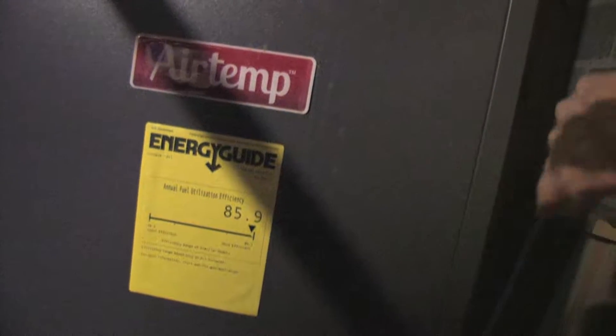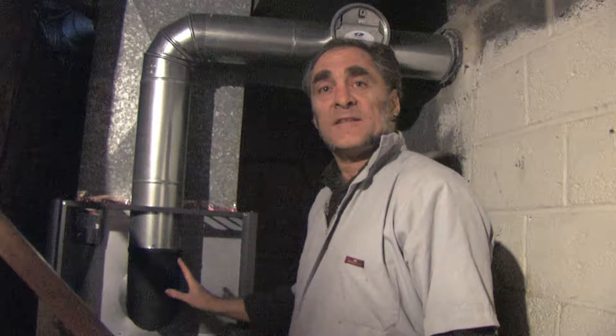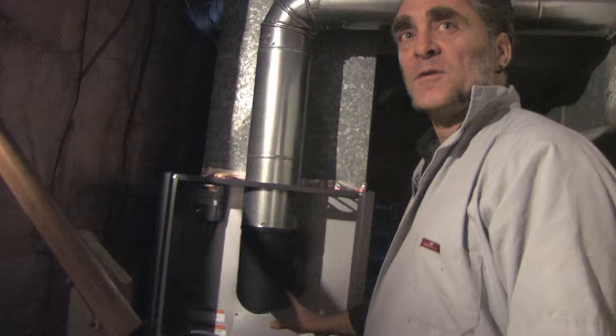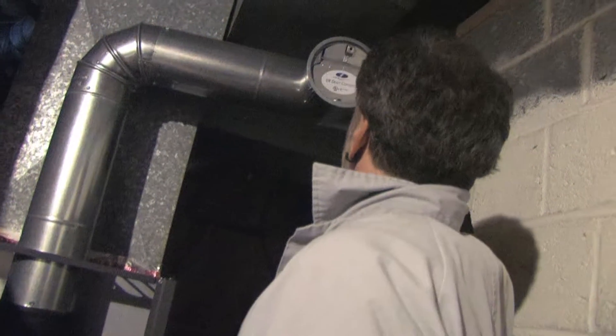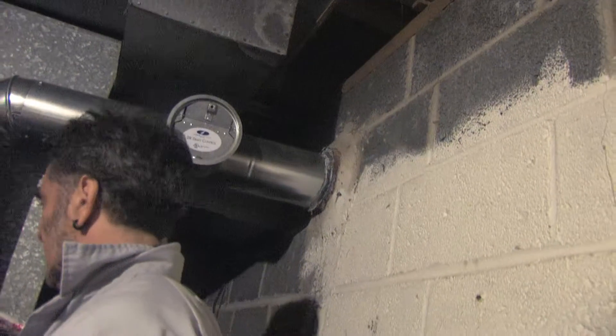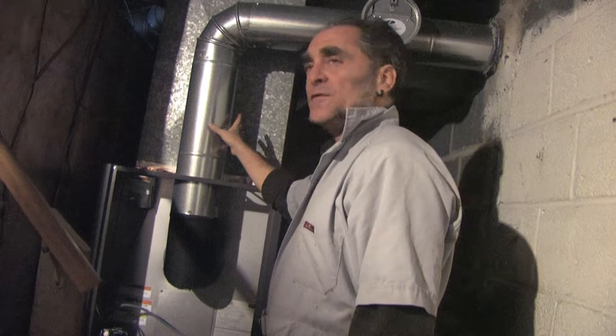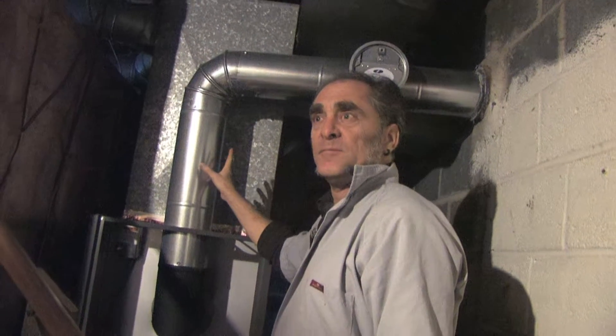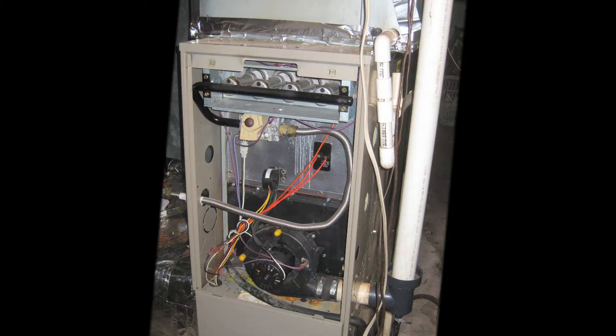In terms of today's technology and an oil-fired furnace, that's the best you can get. What you know for sure as soon as you walk up to a combustion furnace is that it's burning a fuel — oil, natural gas, propane, or kerosene. The way you know is because there's a flue pipe coming out, going into the wall and up the chimney. If there's no flue pipe, there's no combustion. And if the flue pipe is plastic — usually two-inch white PVC — that means you've got a 90-plus furnace, because it's so efficient the gases aren't very hot, so a plastic pipe is okay.